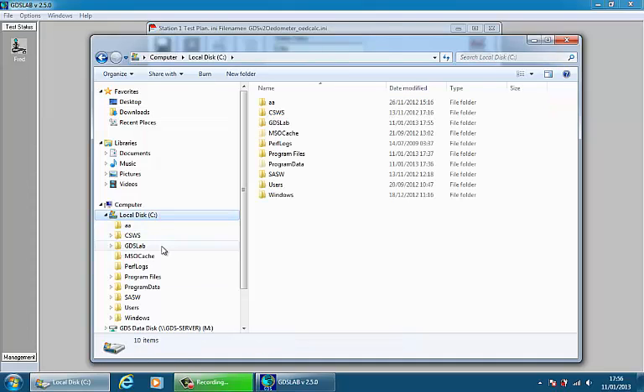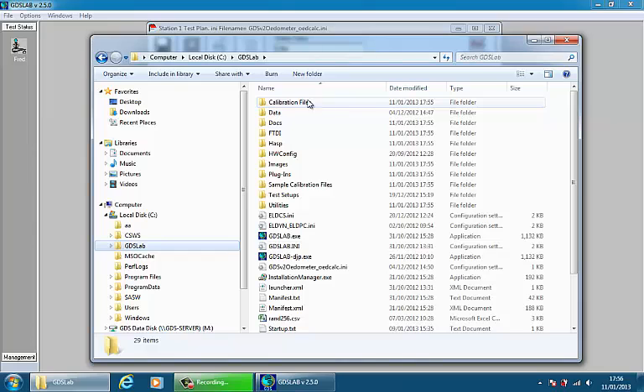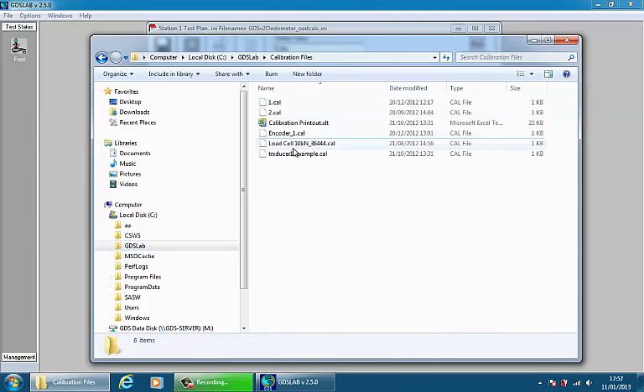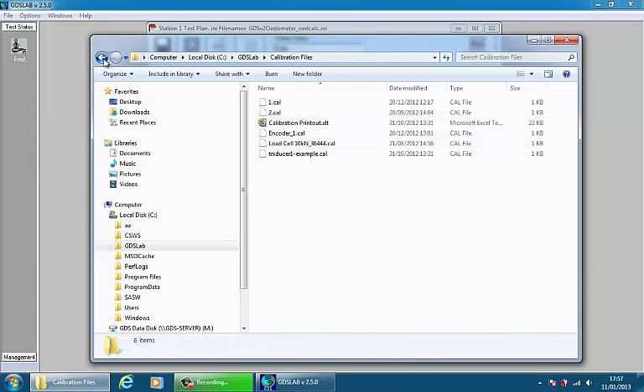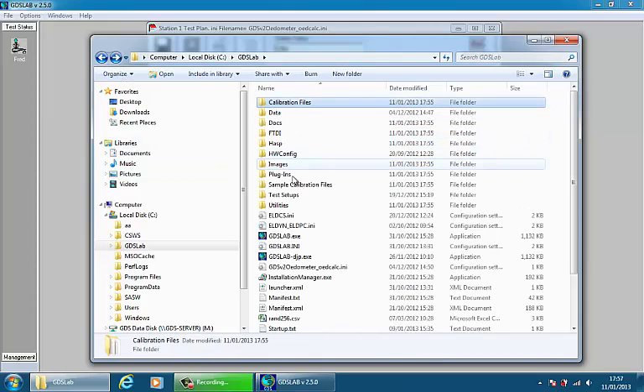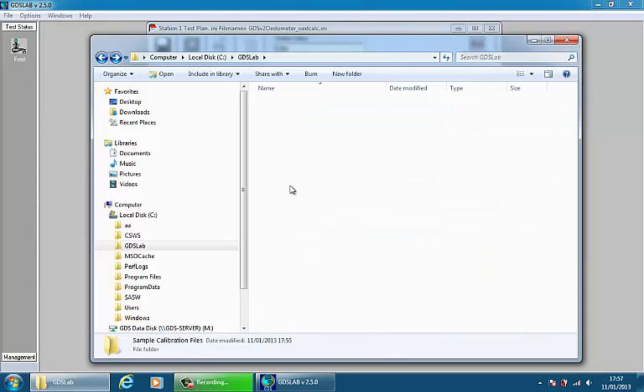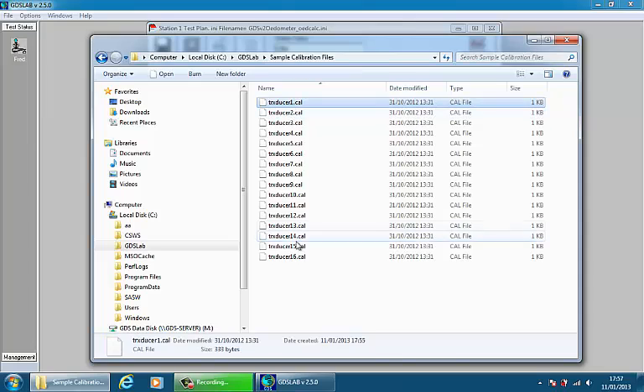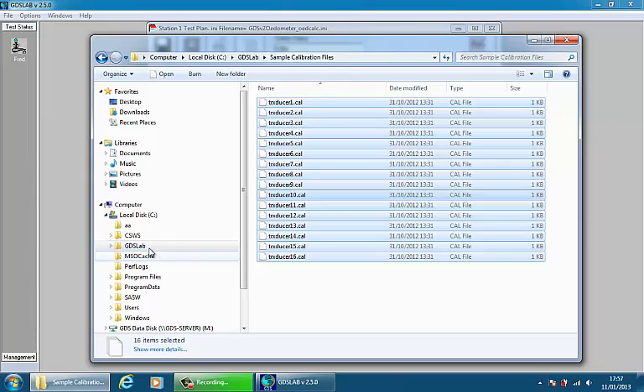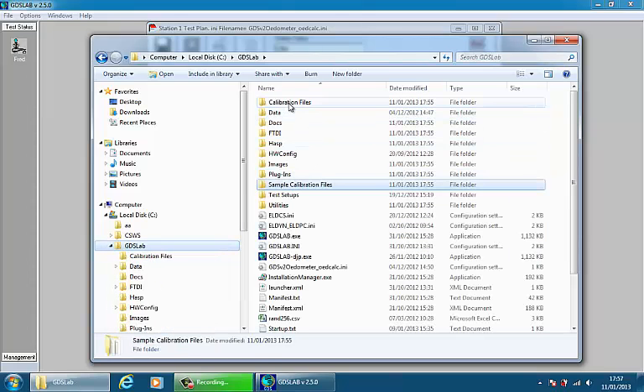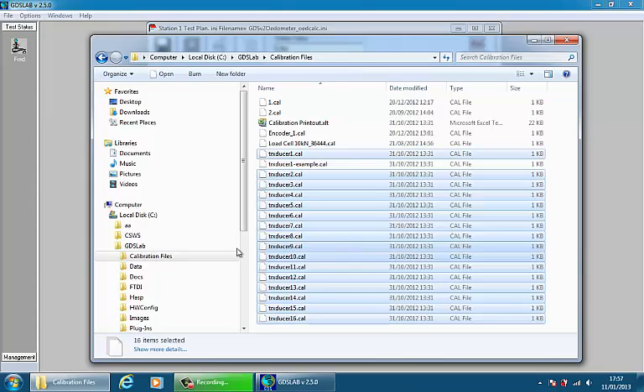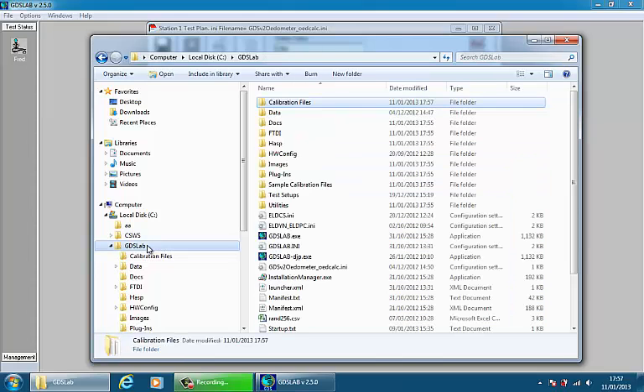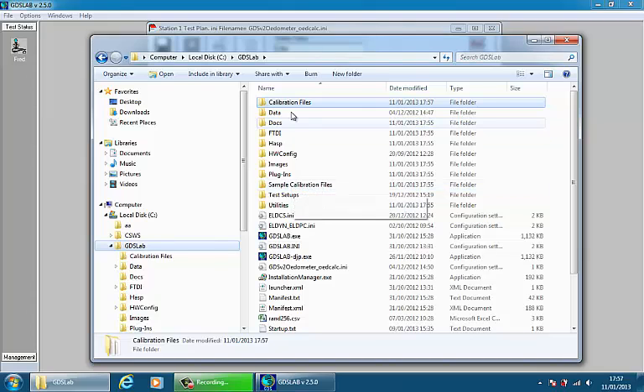Now, it will be important to show you on this machine that within the GDSLab directory, we have the calibration files directory as normal, which houses calibration files for your initialization file. When it does the uninstall with versions 2.5 and above, it does not delete, remove, or modify any of the files within this directory. What it does is it puts calibration files within this sample calibration files directory so that they can be copied over. If your standard .ini file has any of these .cal files that it's expecting, they can be copied over to this calibration files directory. So just to reiterate, when you do a reinstall with version 2.5 and above, it will put these sample calibration files in place. It will not touch your existing calibration files.